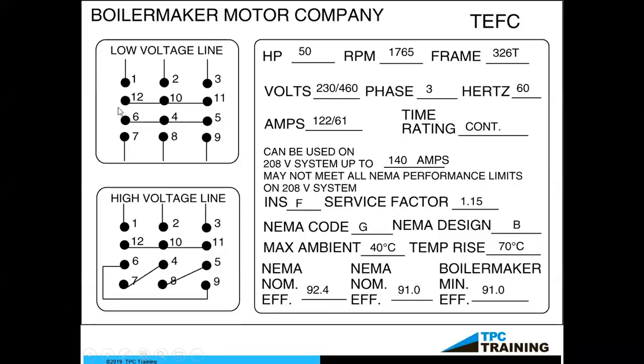So over here on the left-hand side where we show you the different connection points, what we really want to give you an idea about is when you have a dual voltage motor like this, basically when we connect it to the higher voltage, we're taking each winding and connecting those in series with each other. Because in a series circuit, we know that the voltage adds up to the total. So if I took, for instance, the A winding, and I cut that A winding right in half, but I connected each half in series, then I would have 230 on one half, 230 on the other half. It would add up to my 460.